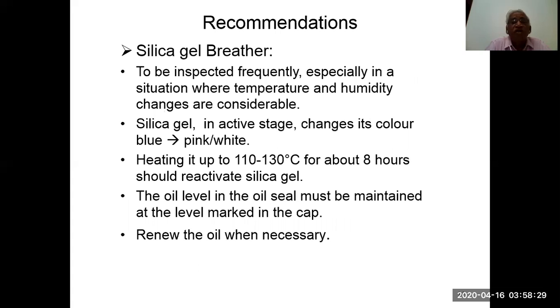The silica gel breather is to be inspected frequently, especially where temperature and humidity changes are considerable. Silica gel in its active stage is blue; when exhausted it changes to pink or white. Heating it to 110 to 130 degrees for about 8 hours should reactivate the silica gel. The oil level in the oil seal must be maintained at the level marked on the cap. Renew the oil when necessary.